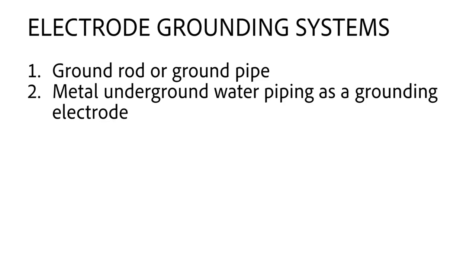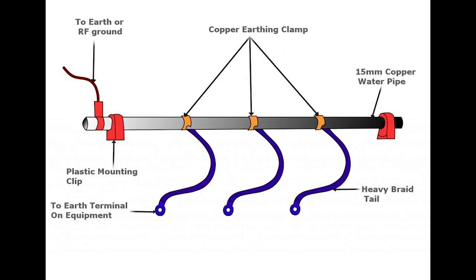Next is the use of metal underground water piping as a grounding electrode. It is required that this pipe be in direct contact with the soil for at least 10 feet. It is also required that a supplementary ground rod be used with this type of system in order to meet NEC requirements.